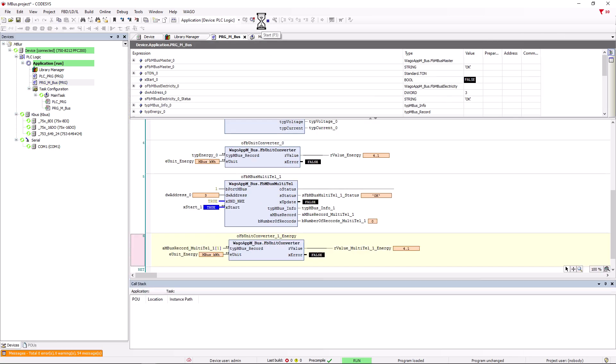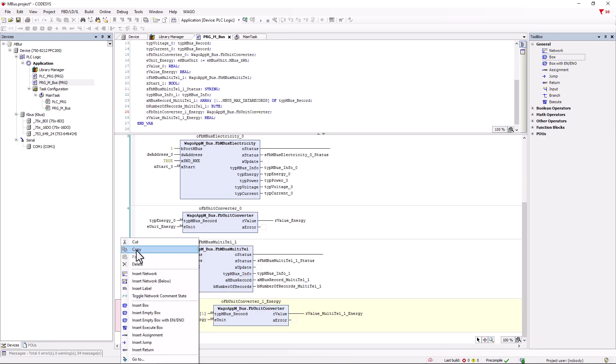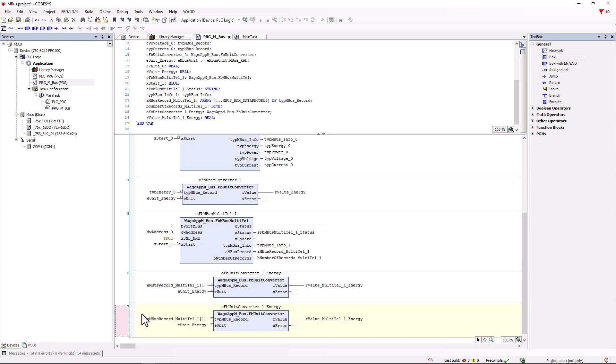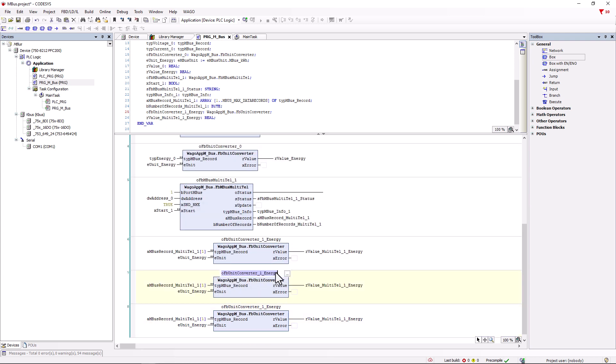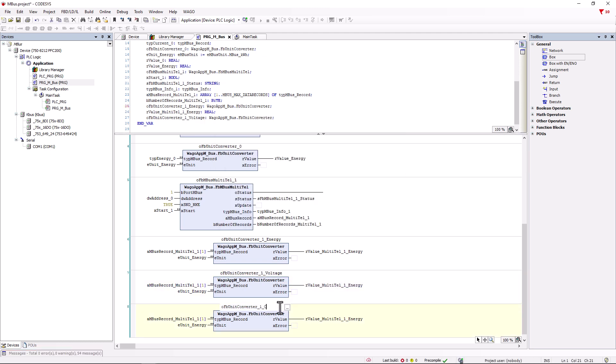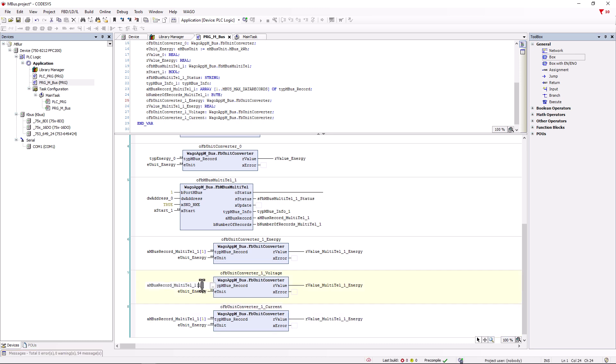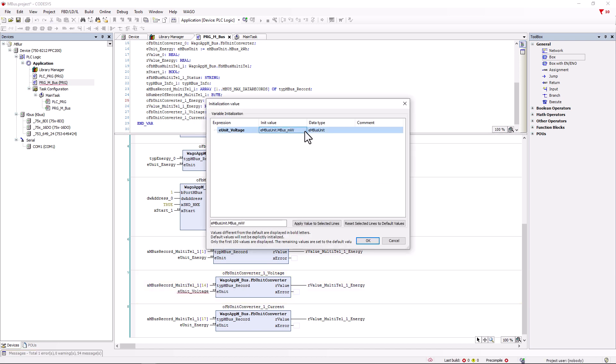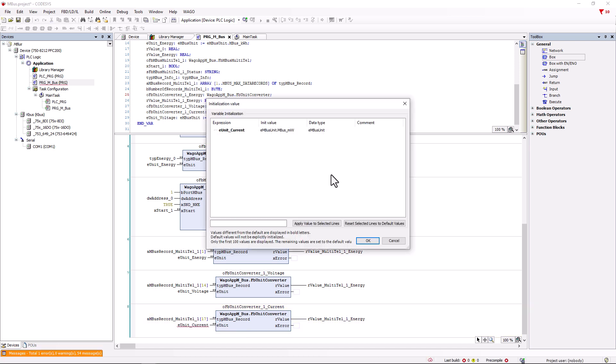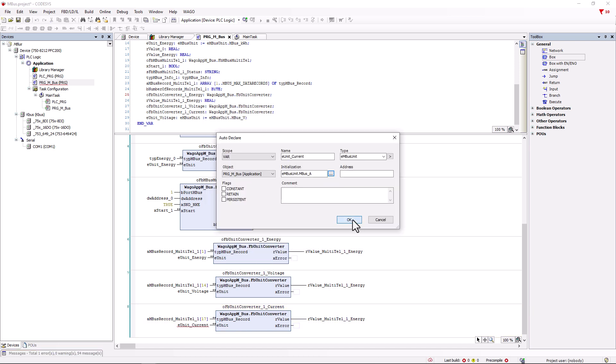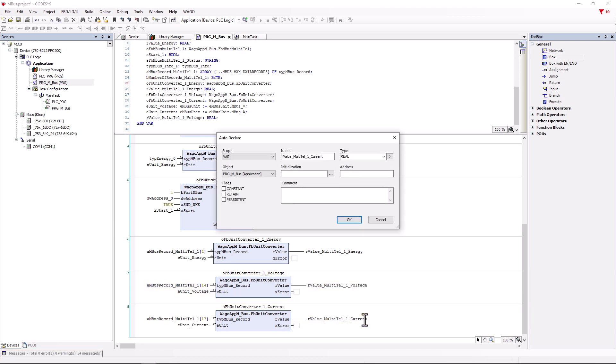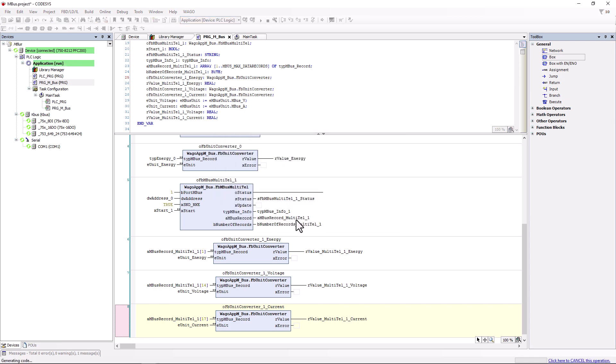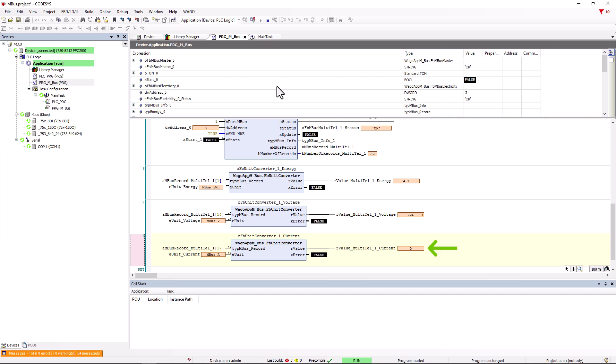And we can read out the energy in the correct unit but now via the Multi-Tel function. In order to read out the other values, for example those we cannot read with the electricity module, we create two new networks with copy and paste including the unit converter and change the names and array positions. 14 for the voltage in phase 1 and 17 for the current in phase 1. In each case a corresponding variable for the unit and output is also created and we can test the application. The three values are displayed to us and if we now switch a load on L1, the current in L1 also increases.